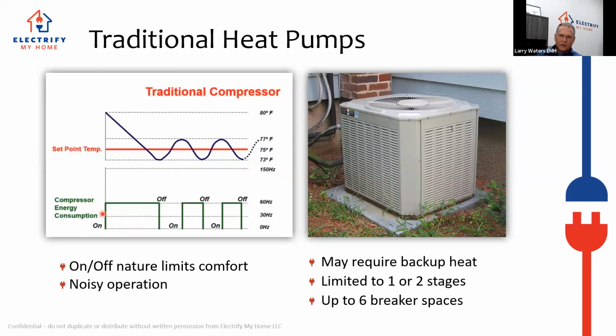If you're running off batteries and you're starting something that uses 40 amps, even if it's just inrush current, that could be a problem. And then they use a lot of energy running until they get the house colder than they want it to be. And then they shut off, and then they let the house get warm again. So this is not good building science or energy science here. We don't want to cool the house off and let it get warm again, because we're just going to use a bunch of energy to cool it back down again and keep this on and off scenario going. This is really wasteful on energy, and it uses a lot of energy to start.